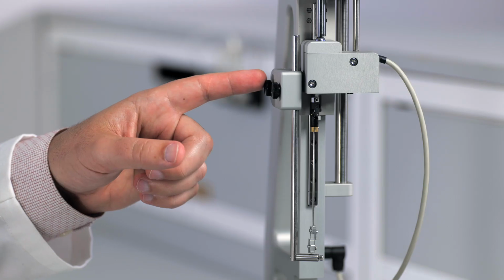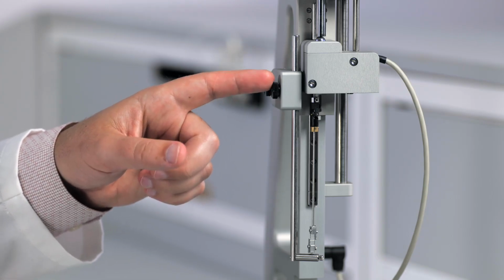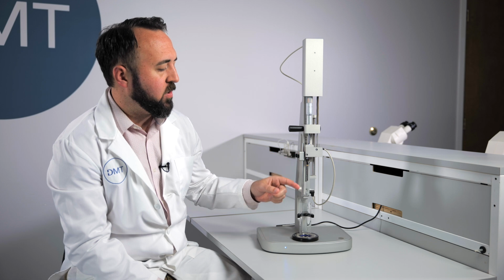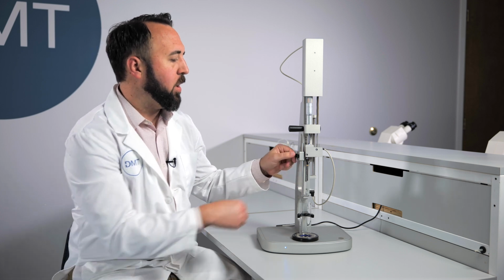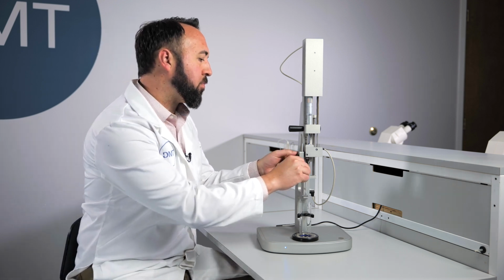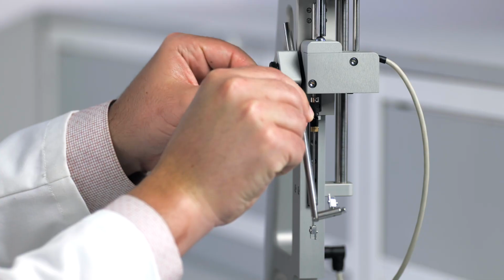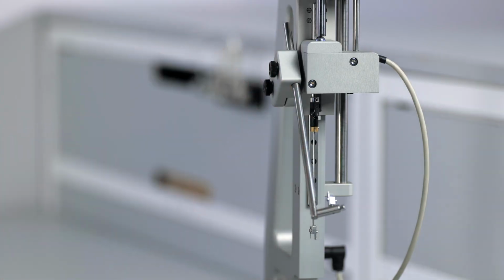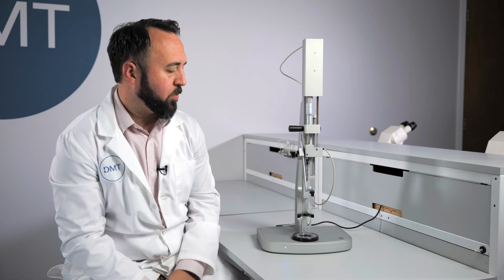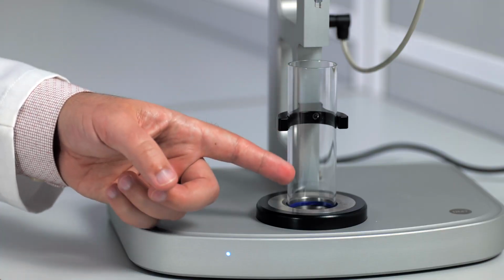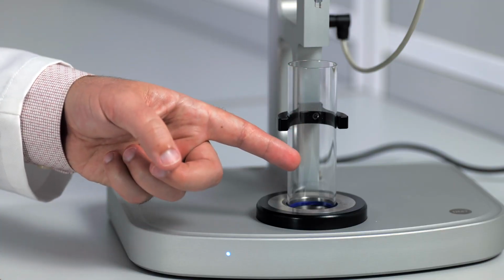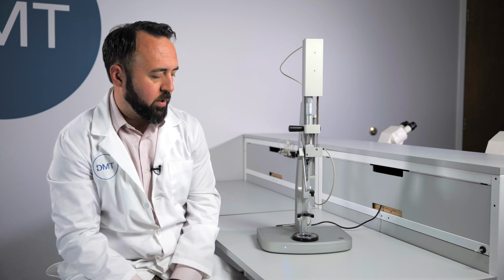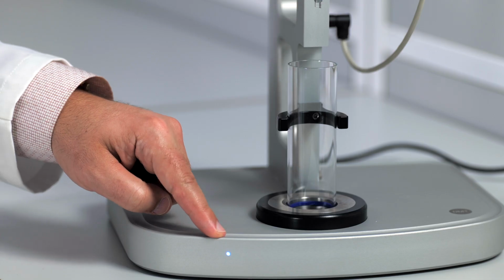You can see 2 mounts on the left side. The first will allow you to raise and lower the bottom section. The second allows you to get this mount out of the way so you can perform a force calibration. You also have a glass tissue chamber which can easily be removed to clean or be autoclaved. And you also have a blue indicator light showing power in the system.